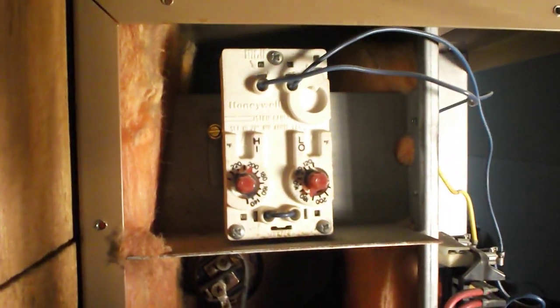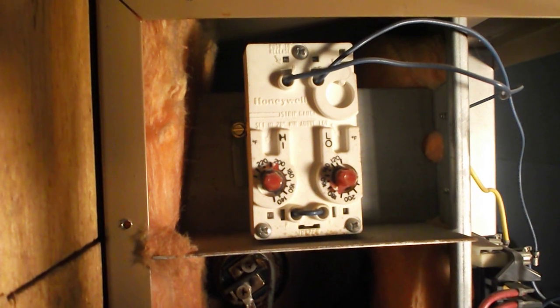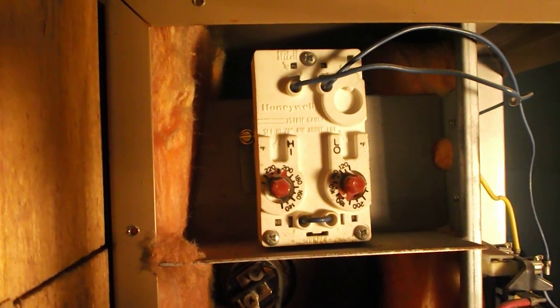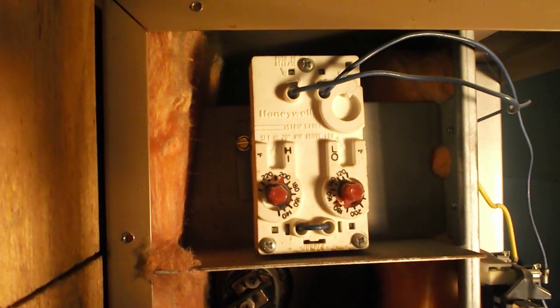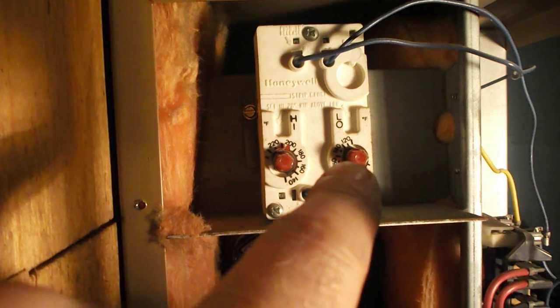And if we move over on this side, connected to the blue wires is a temperature control for the boiler itself, and it has the control temperature where the boiler elements will cut in, and then when they get too hot, they will cut out. So there's the low control and then the high temp control.